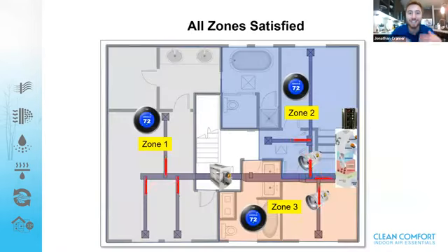Well, that simple technique and that simple thought process sounds silly, but let's apply that same logic to now our HVAC and zoning equipment. So let's say that we have a 3-zone system that we just set up in this brand new house with our homeowner, and they're excited about it. And we're now going to set it up, but we did not install a bypass. So this is for not having a bypass, not having anywhere to regulate that static pressure. We just installed the zoning equipment and said, hey, I'm not going to worry about it.